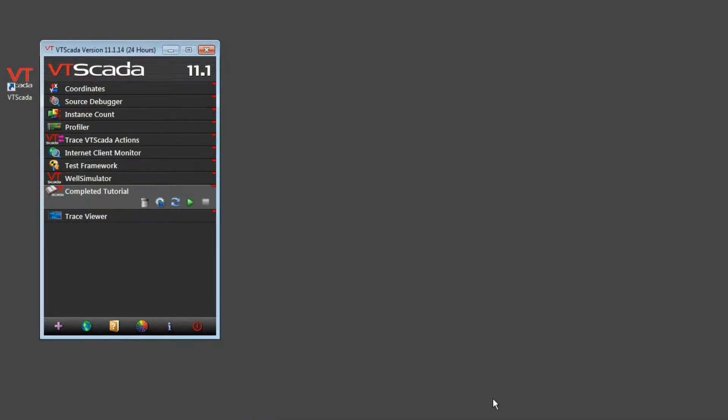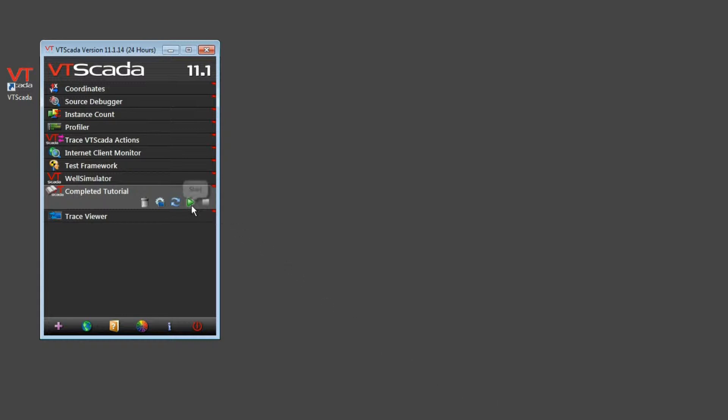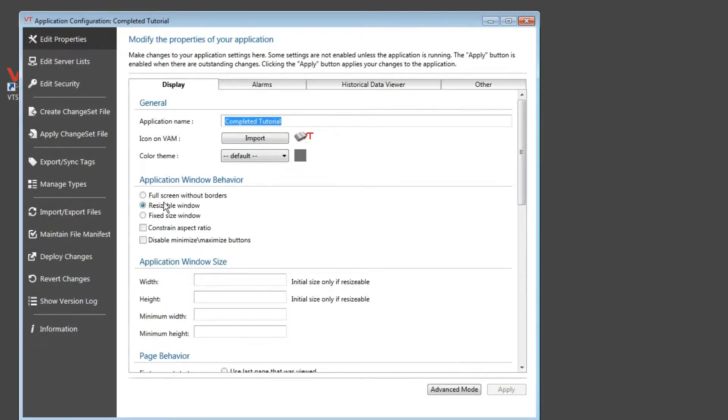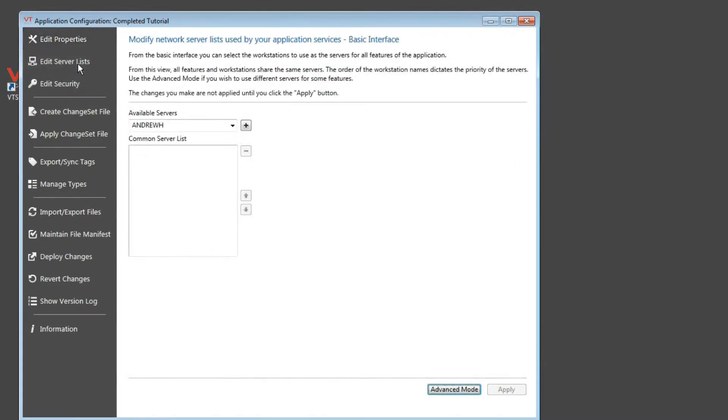Now to configure a primary server, you don't need to install extra software. You don't need any extra hardware. You don't need to configure anything in VTScada itself. All you need to do is the following. I'll just demonstrate this with the tutorial. What I do is open the application configuration and then go to the Edit Server Lists tab. Your computer will be the first one in the list of available servers. If your network has a properly configured domain name server, all the servers on the network will be populated in the list.